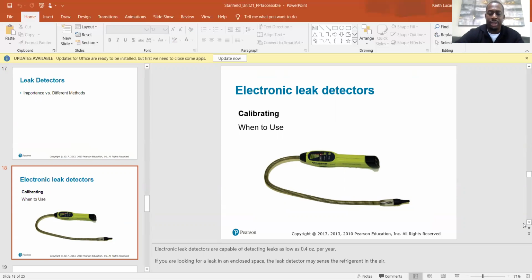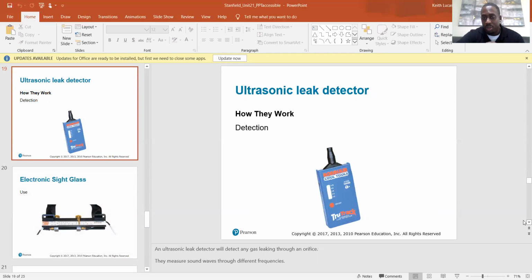They can get you in a general area, but let's say it's in an enclosed area and it's been leaking for quite a while, as soon as you enter the room, that thing might start going off. So you're nowhere near pinpointing that leak. But you can get in the general area because the intensity of the beeping will increase the closer you get to the leak. Then you've got to pull out your soap bubble and start spraying stuff, because the soap bubble is the only way to pinpoint the leak.